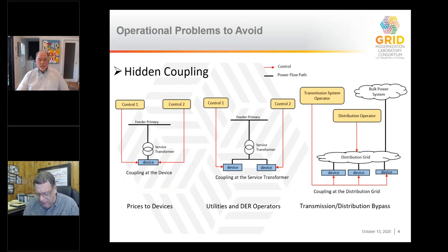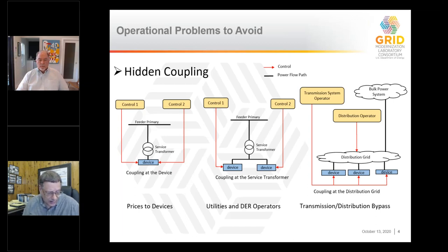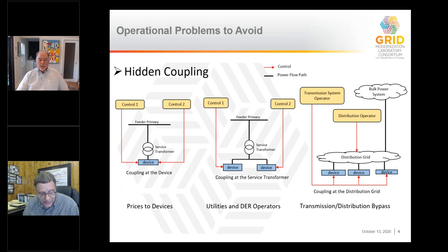One of the things that can happen is hidden coupling, and it can occur in a number of different ways. For example, if you have a device — a rooftop solar inverter, a storage unit, or any number of things behind the service transformer — and you have two different processes trying to control it, such as two different processes using price-based methods, they can end up fighting each other, in conflict if there's no coordination between them. We've actually seen this happen with one process overwriting the prices left by another. Another way this happens is two different control mechanisms manipulating devices on the same service transformer secondary, creating conflict — we've seen this with utilities controlling some assets and DER operators controlling others.